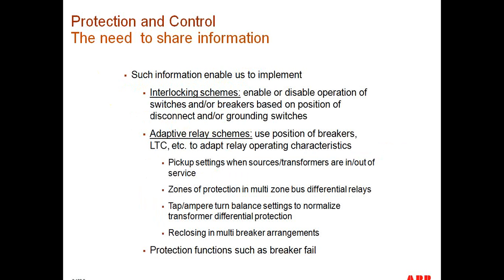And the way that information is shared is in the form of cable connections from those devices or apparatus onto protection and control IEDs. Here are just some example applications. Interlocking schemes based on the position of disconnects or grounding switches enable or disable the operation of other switches and circuit breakers. This is one application. The position of breakers or disconnects can also be used for enabling or disabling certain protection functions. Okay.